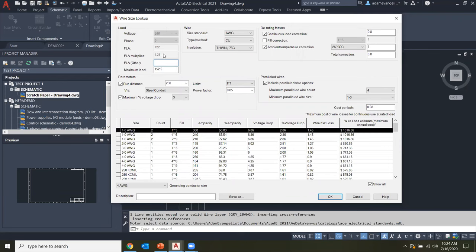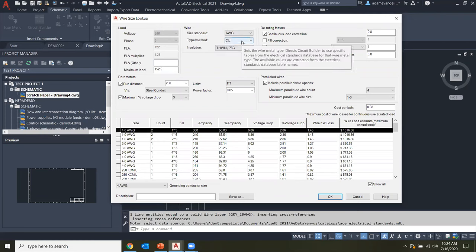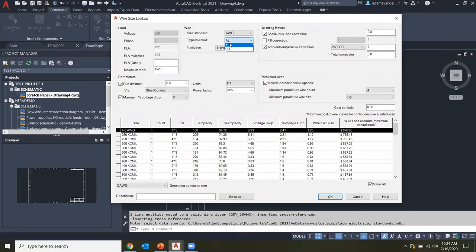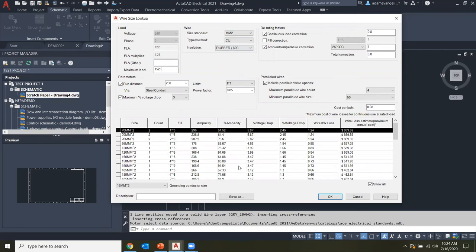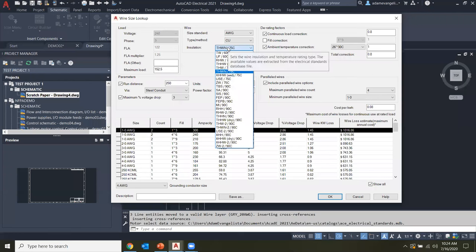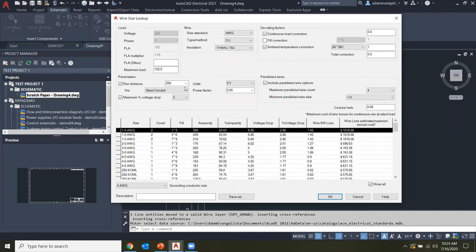The voltage, phase, and FLA all came from the motor selection and are locked in here. Once your load is finalized, you can go through and choose your wire standards. AWG is American Wire Gauge, and MM2 is the metric millimeter version. You can choose copper or aluminum, and a different type of insulation if you prefer. Choose copper and the appropriate standard, and once the wire standard is set, you can go about your business. There are also derating factors you can specify — environmental factors affecting the efficiency of your wire.